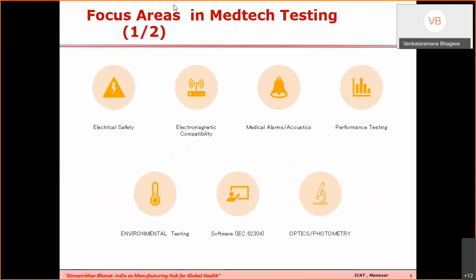So what I have done in this slide is I have encapsulated about 14 kinds of different tests which are used for medical devices in general. The first one is electrical safety on the top left. As you can see, most of the devices which use electricity, like active medical devices, there are about 500 to 600 active medical devices as per the US FDA list. For them, this electrical safety is very critical, specifically because for a patient, already his health is kind of compromised. And therefore, the limits for leakage currents or dielectric strength are all very critical. Otherwise, it may cause harm to the patient.